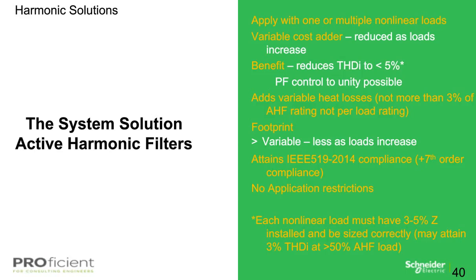Okay, very good. So I will move quickly through the next couple slides here, and just spend a real brief time covering the final application. Using more of a system approach, again, some of the active harmonic filters can typically be used on one or multiple nonlinear loads. The reduction here is THDI to under 5%, and PF control to unity is possible. This adds variable heat losses of no more than 3%, and it does attain IEEE 519-2014 compliance even beyond the 7th harmonic order.